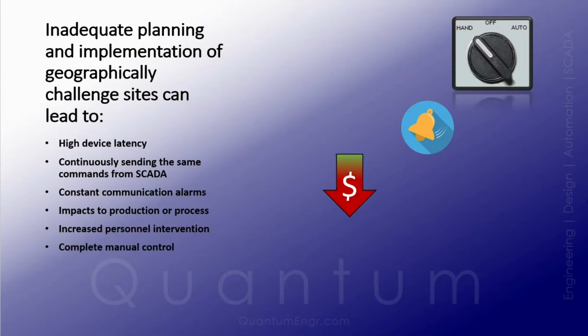The other thing you see is constant communication alarms coming across the alarm banner: this site dropped out, that site dropped out. Eventually operators get fatigued and they ignore those, and that's really bad.